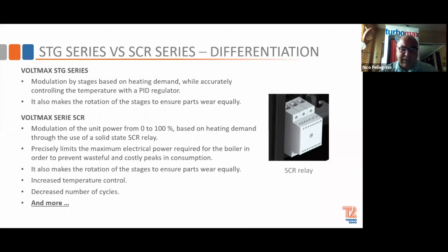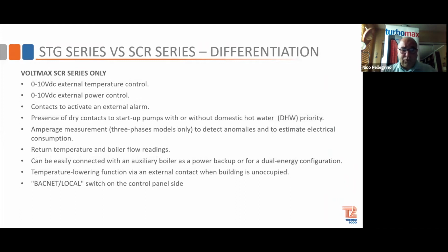So we can actually control it by 2 different 10-volt DC controls. We have one that you can control on a temperature base, or one you can control on power control. So if you want that boiler to run at 80% all the time, you just program it in, put a 10-volt DC on it, and it automatically works.